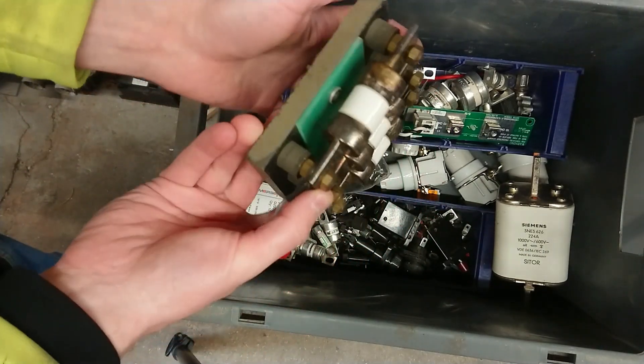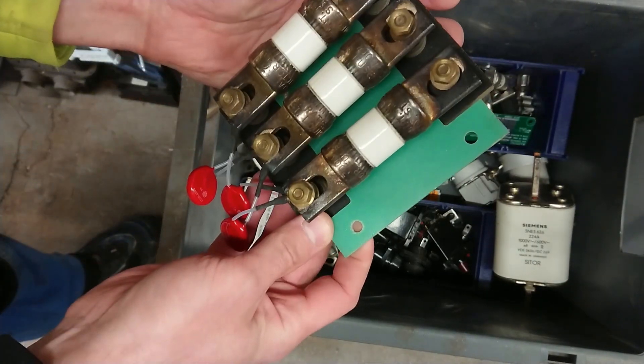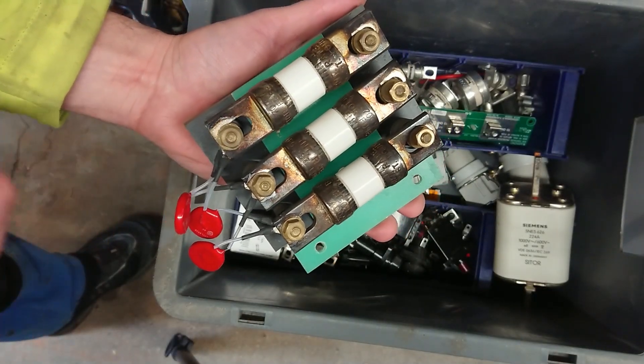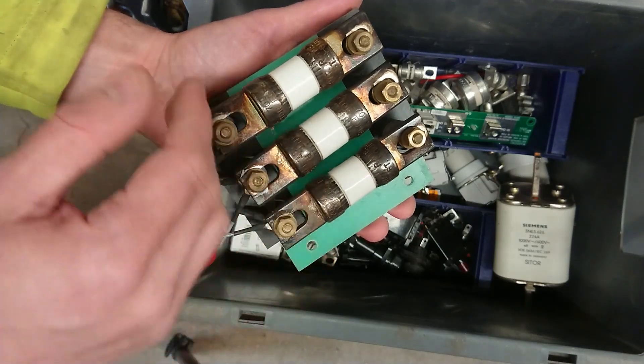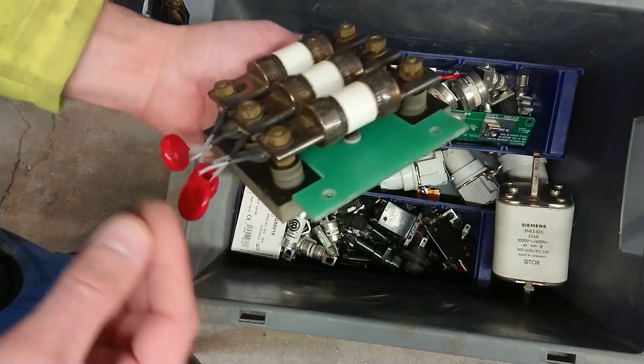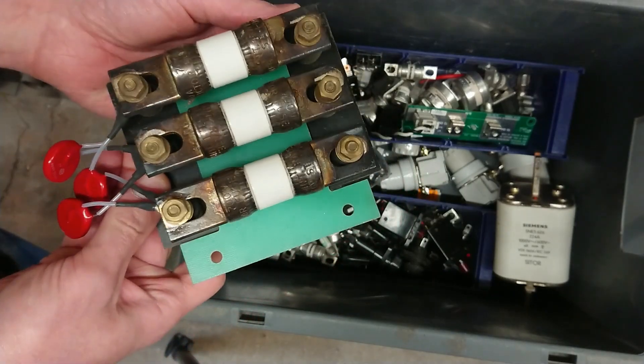Some smaller also inverter fuses. These are rated at 700 volts and 20 amps. As you can see, those are pretty large for 20 amps. The heat discoloration you can see has to do with them being fast blow fuses in semiconductor operations. These operate at the brink of melting - so these are maybe 250 degrees Celsius hot when running a full 20 amps, and if you go to 21 amps it will melt simply because the silver thread inside is glowing white hot.